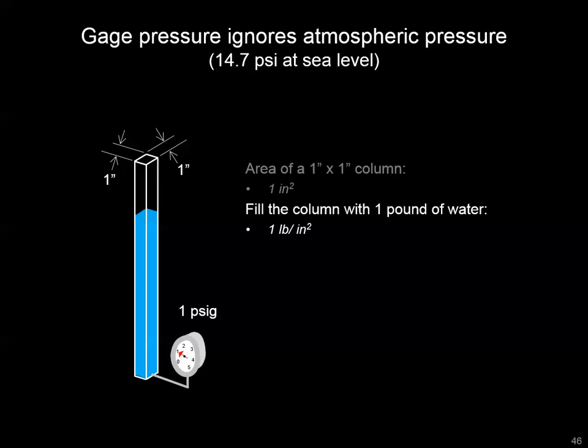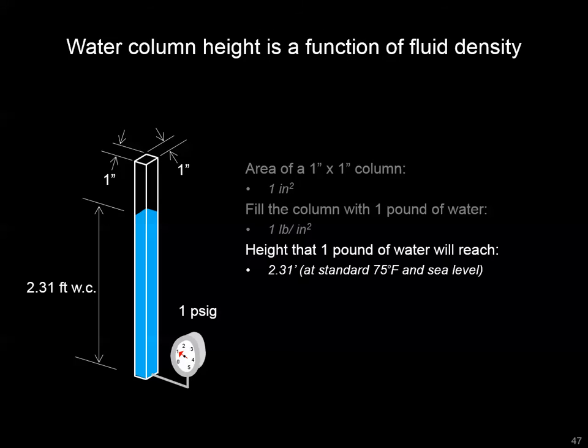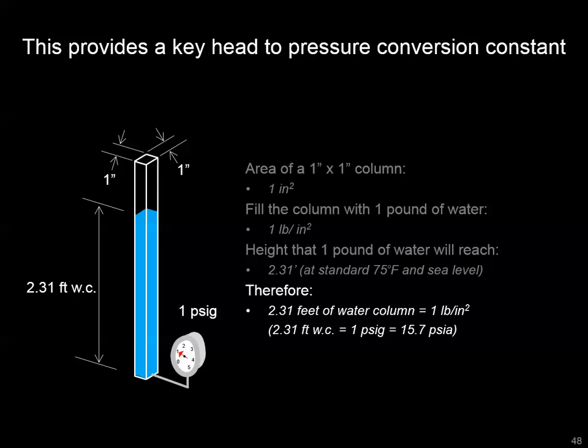We use the term gauge to qualify psi because there's always atmospheric pressure crushing down on the water. At sea level, that's about 15 psi, so gauge pressure ignores that — that's why we say 1 psig, or pound per square inch gauge. Now, if you measure up that column of water, you get 2.31 feet at these ideal conditions. That's the source of the key conversion: 1 psig corresponds to 2.31 feet of water column.